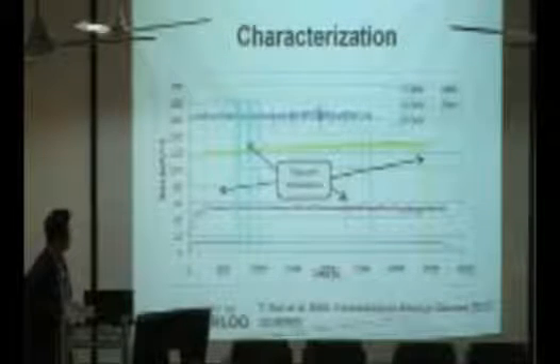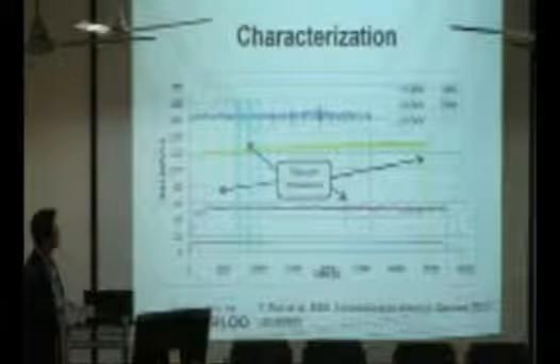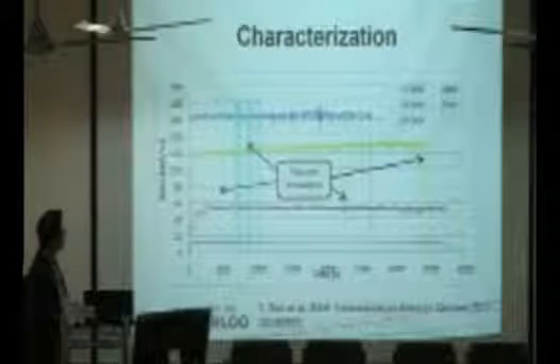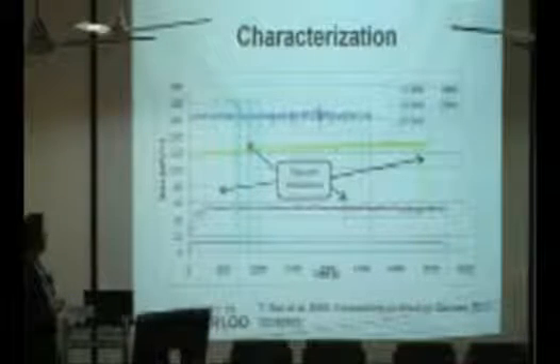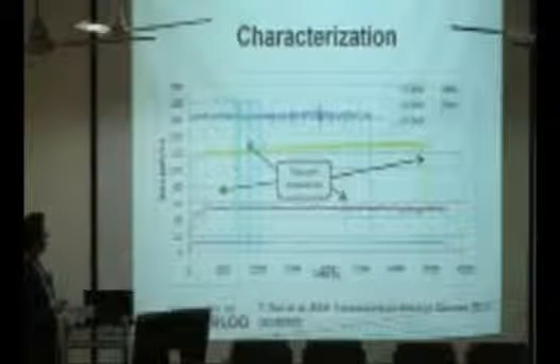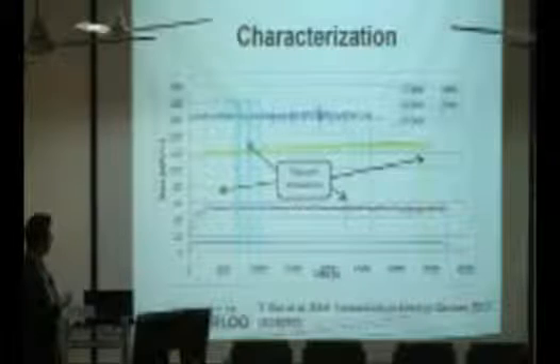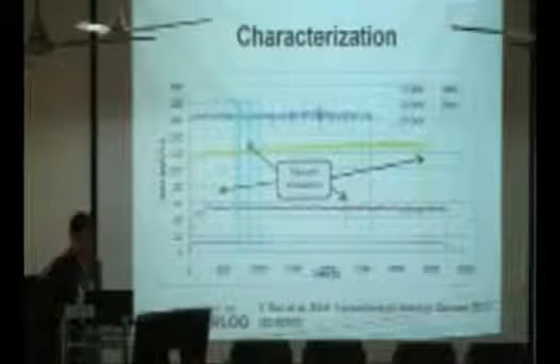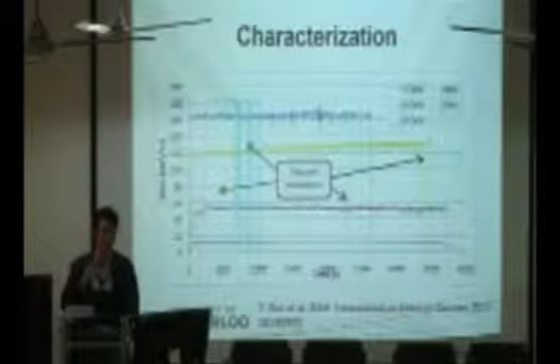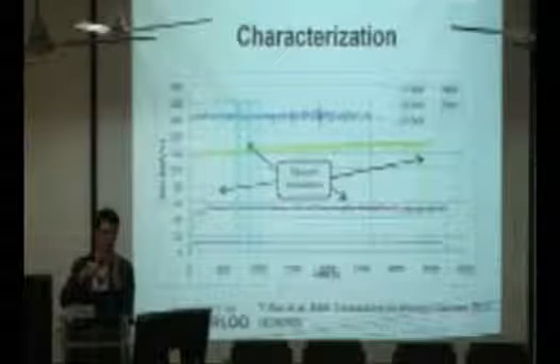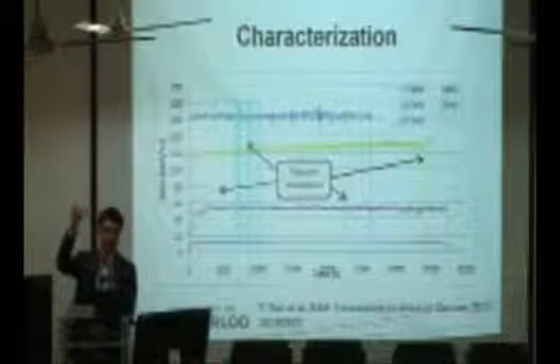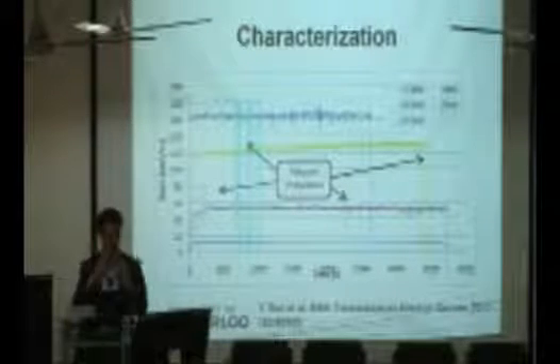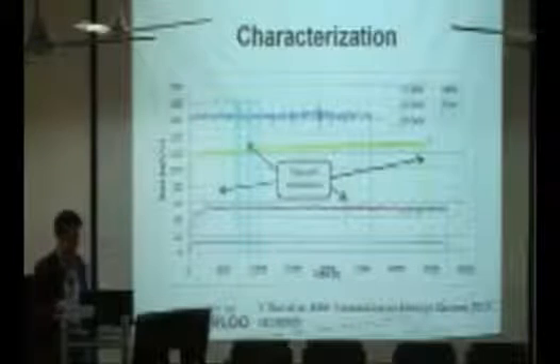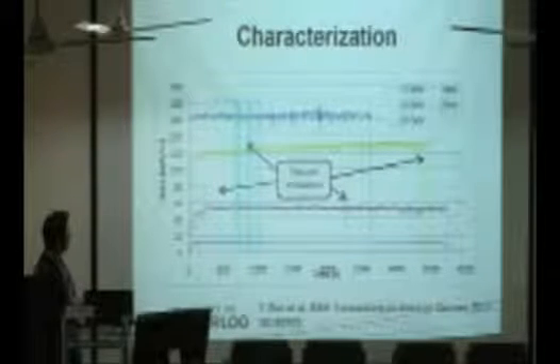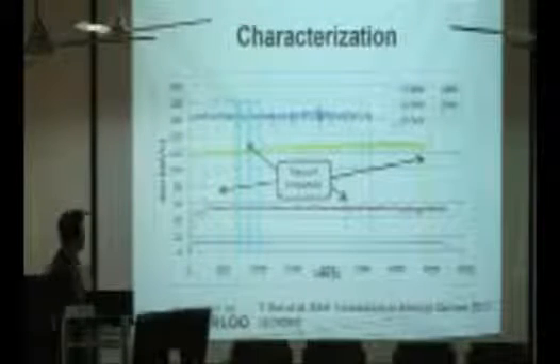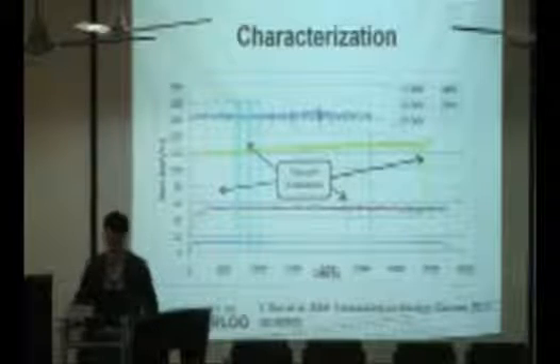We have not done therapeutic X-ray yet. This is in the kilovolt range, so it's more for a diagnostic application. We have it running at as much as 27 or close to 30 kilovolt, and you could see instability here. The instability is caused by the outgassing of carbon nanotube. At this point, carbon nanotube is still burning off. As it burns off, it's releasing carbon material into the vacuum chamber, and that would degrade the quality of the X-ray. But we're confident that at the level of 25 kilovolt, we can create really stable X-rays.